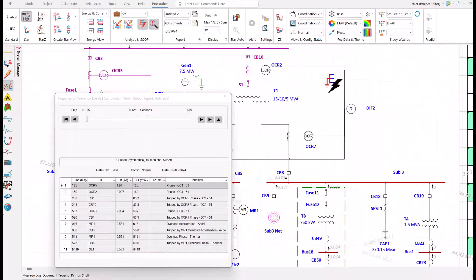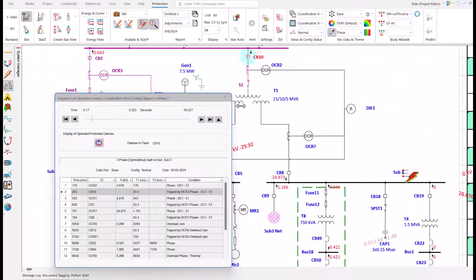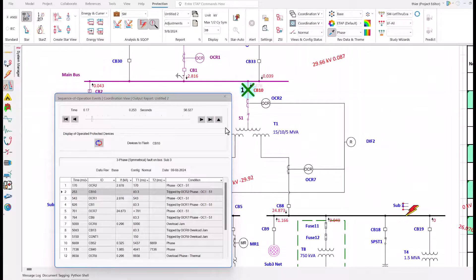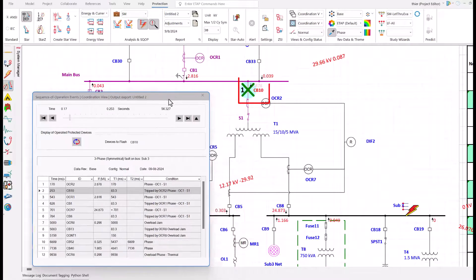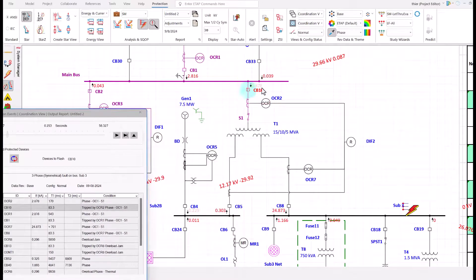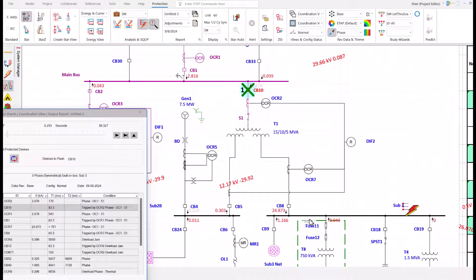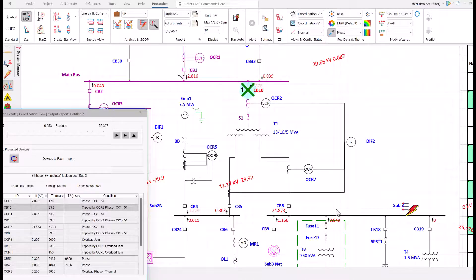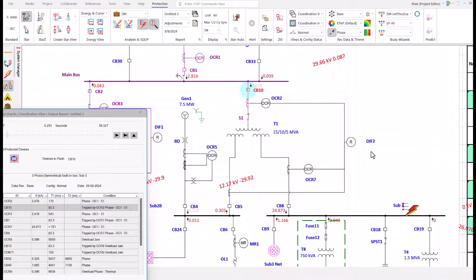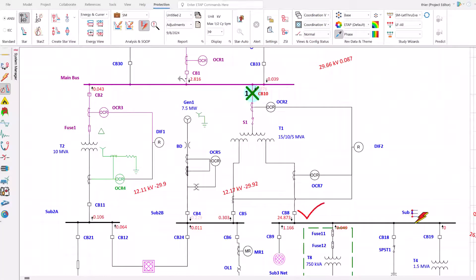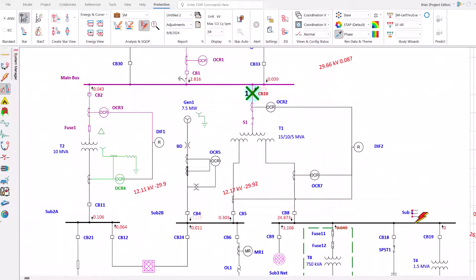Fault at sub 3. CB10 opens. Not good. Why? If CB10 opens, we will remove the fault but we will also lose sub 2B. It is not necessary to lose power to sub 2B to remove that fault. We want the first breaker to be CB8. We have a miscoordination. Now we know our flaws and can attempt to fix them. Done. Beautiful. There is no need to read 5,000 page reports.